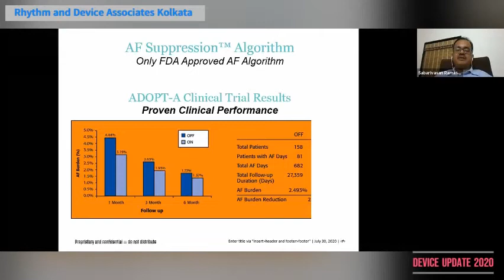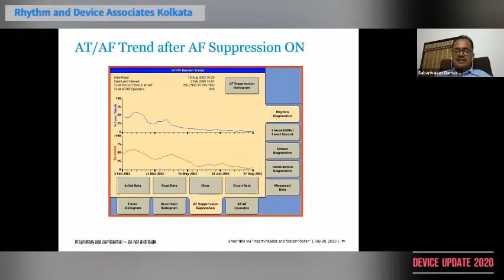And this is the diagnostics which can clearly show how it was before AF suppression. The number of episodes was almost 50, and the time percentage the patient was in AF was almost 50. Then after AF suppression is switched on, it comes to a very low number. So this is exactly the benefit you can get for your patients who have pause-dependent AF. They can be used with AF suppression or similar algorithms which can reduce the burden of AF to a great extent like this.